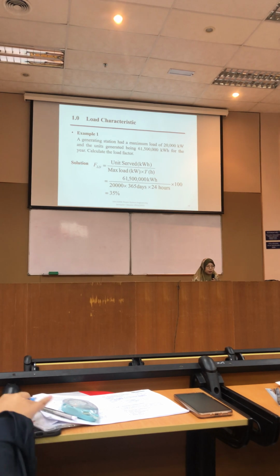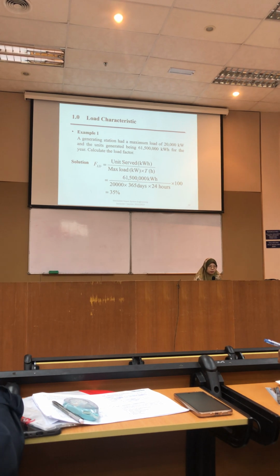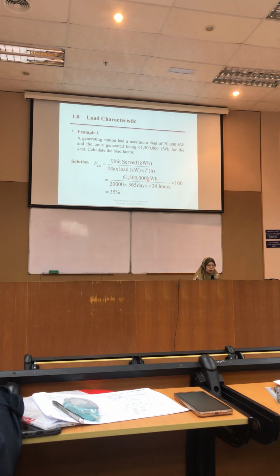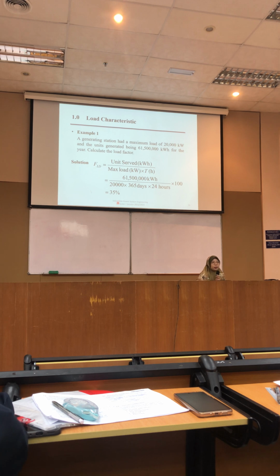So the load factor, okay, the energy that has been served or generated is 61 million, okay, divided by the maximum load, multiply with 8,760 hours per year, times 100, you are going to get the load factor 35%.